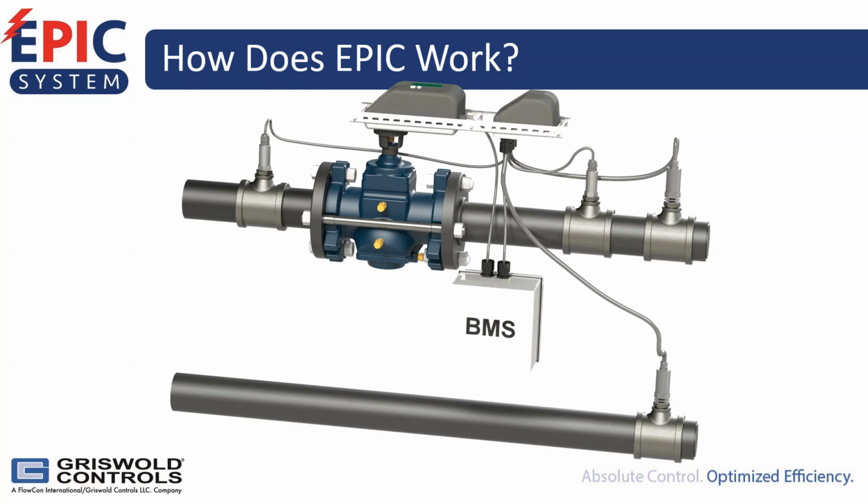The more expanded answer is the EPIC controls the valve based on the delta T across the coil. So the temperature sensors measure the delta T across the coil or air handling unit, and the EPIC controller knows to open or close the valve based on the delta T requirements. So the valve starts to either step open or step close until it gets the heat transfer equipment to the desired delta T. So what happens when the load changes?